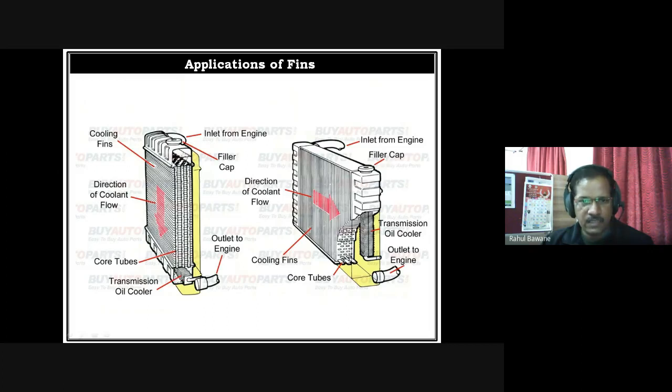And the fins are attached horizontally to the vertical tubes, with a gap in between, so air can flow through these fins. These extended surfaces attached to the tube actually extend the tube's overall surface area. So when hot fluid passes through the tube, it delivers heat to the fins, and when air blows over these fins, it cools down.